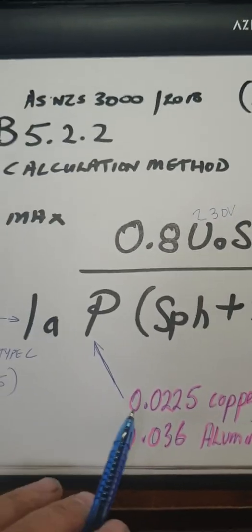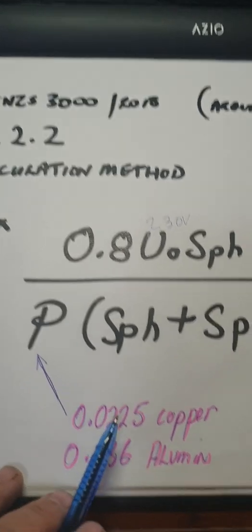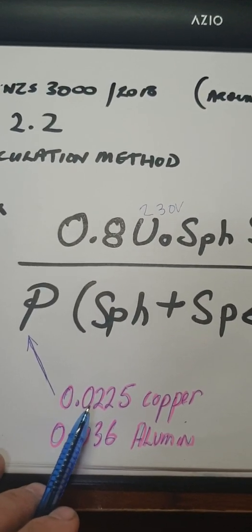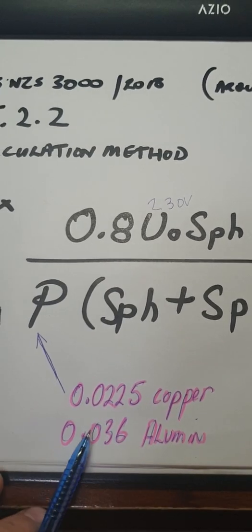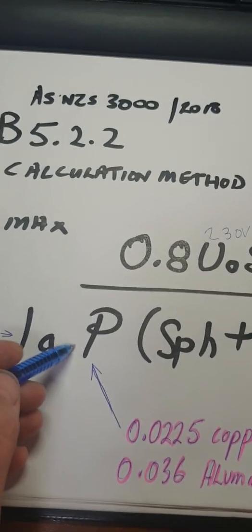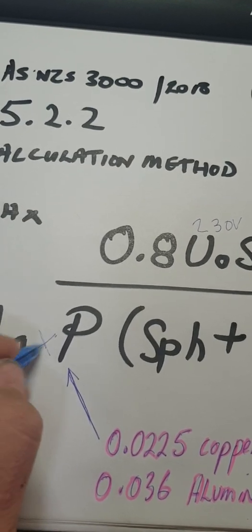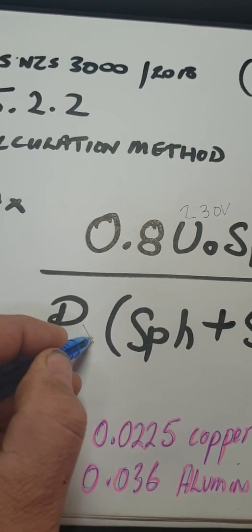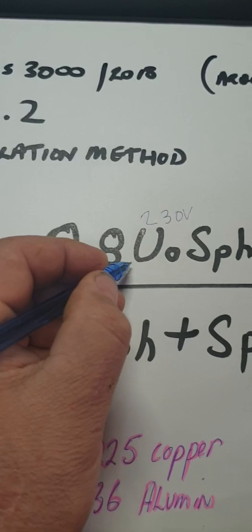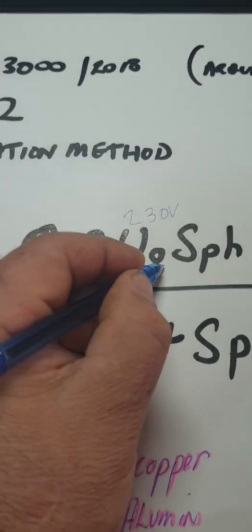For example, if I had a 25 amp circuit breaker times C, it would be 25 times 7.5. Now what's the P stand for? The P stands for if we got copper or aluminium. So 0.0225 for copper.